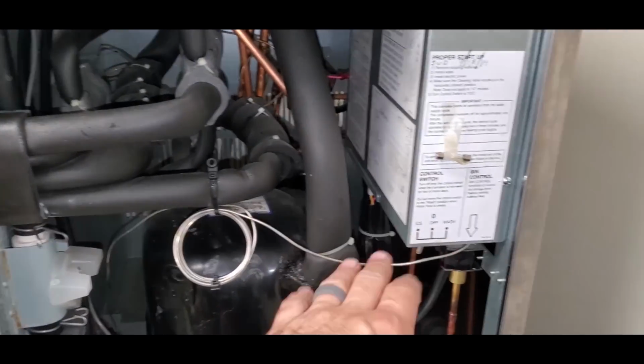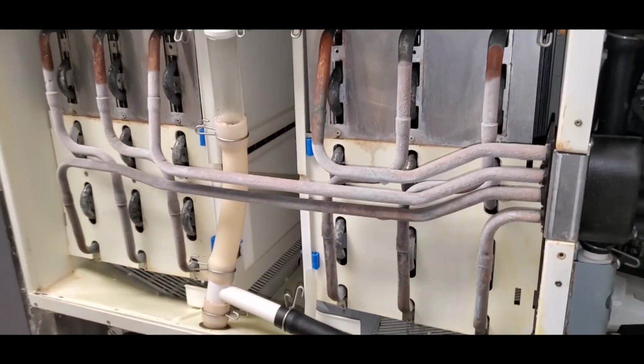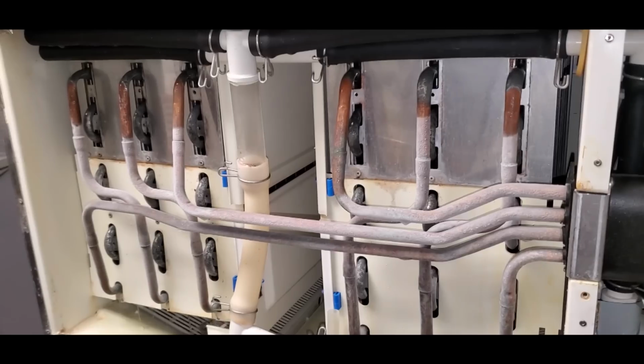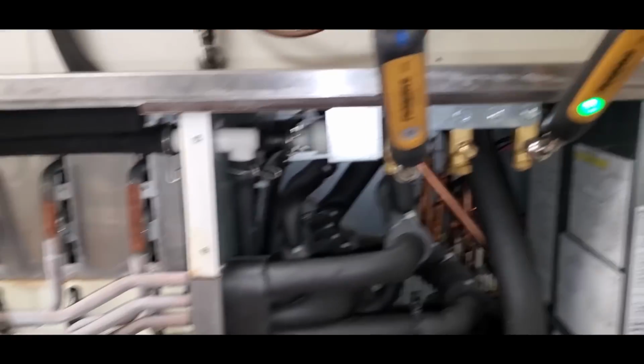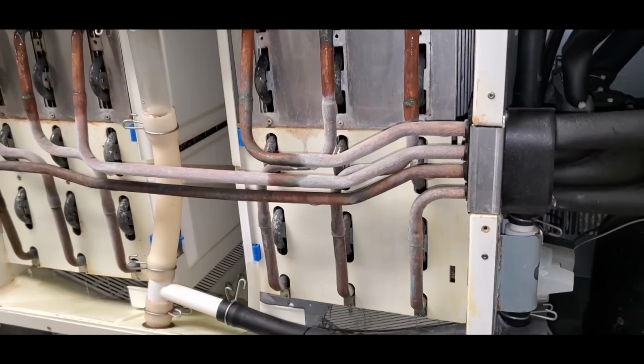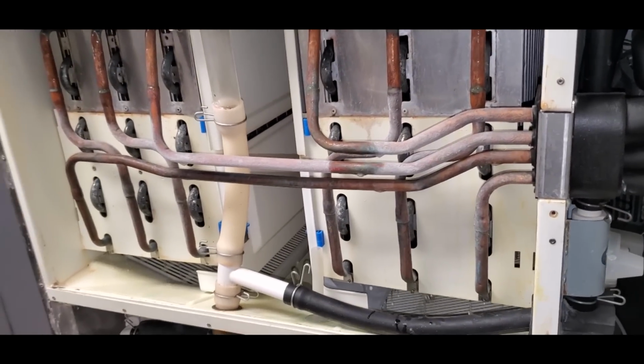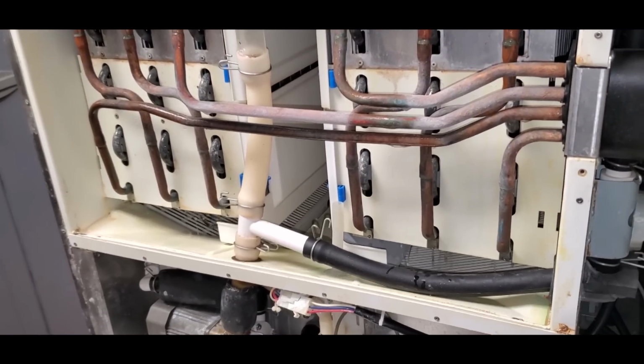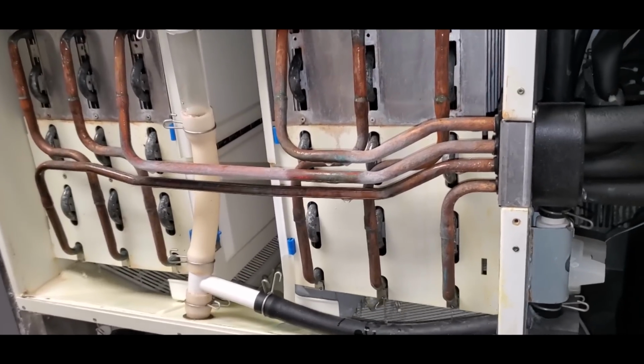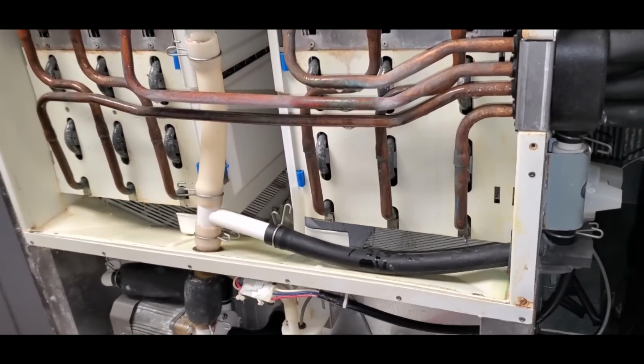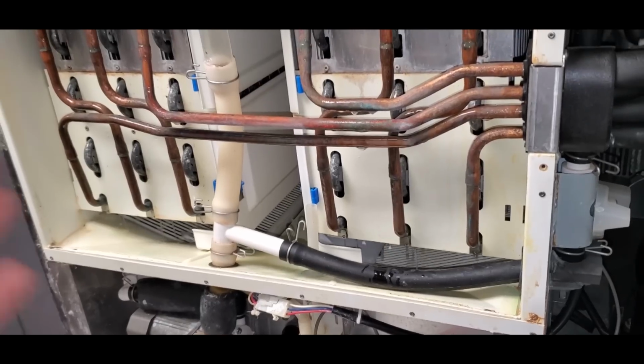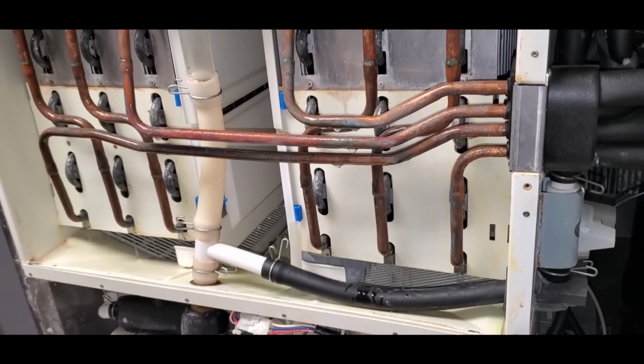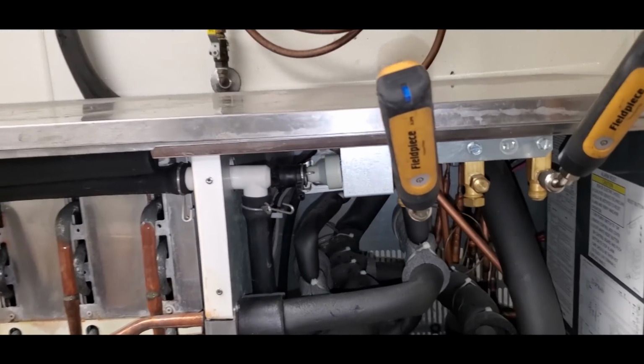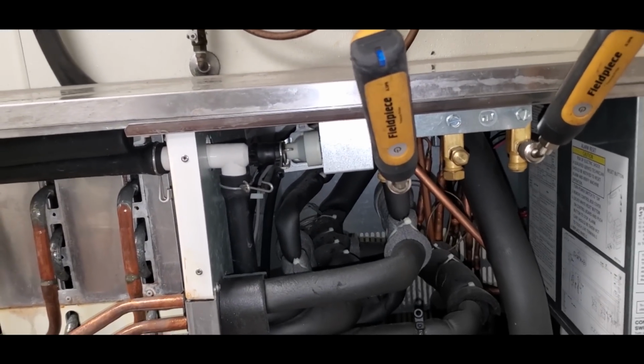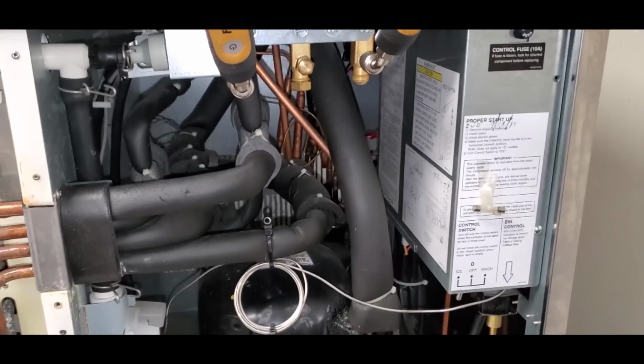What I did was I turned the machine off, turned it back on. That's going to force it into a harvest, defrost all the water off, all the ice off the evaporator. And I'm going to take pressure readings. Hoshizaki wants you to take pressure readings at the 5-minute mark, and it should match up to their tech spec book. So we're going to wait for the cycle to start. Once the water pump turns on, that means that we're in the freeze cycle. Then we'll wait 5 minutes, and then we'll take a reading of the pressures and then compare it to the book just to confirm that we're low on refrigerant, which I'm pretty confident we are.